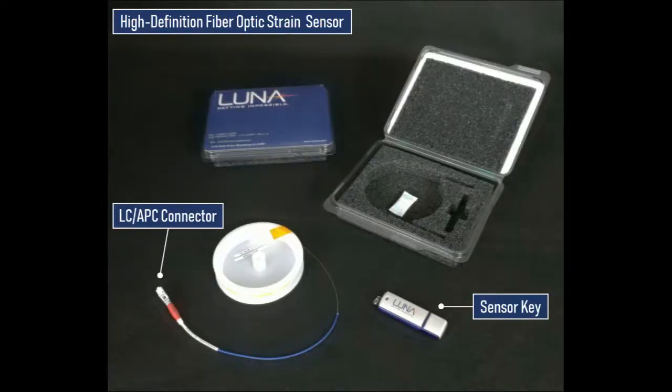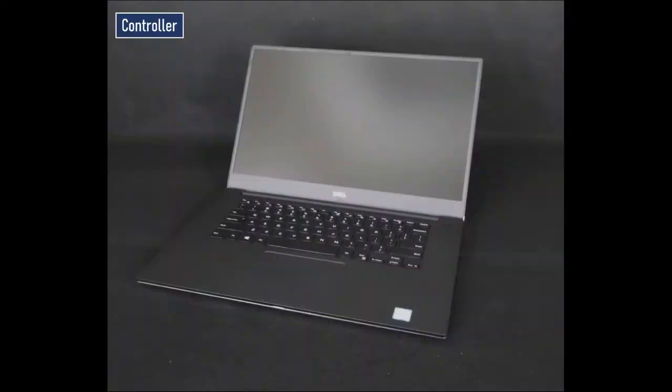Luna fiber optic sensors use LC-APC connectors and each come with a flash drive that contains a unique key file used by the controller to recognize the sensor. The controller is where the user communicates with the Odyssey system, sets test parameters, and takes data.